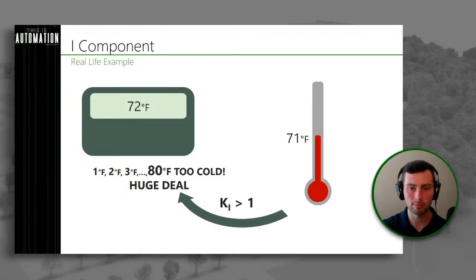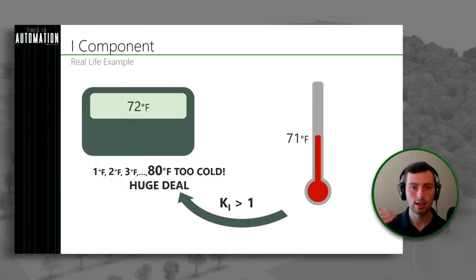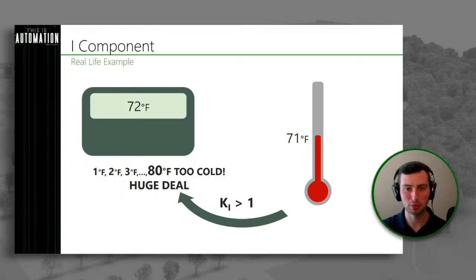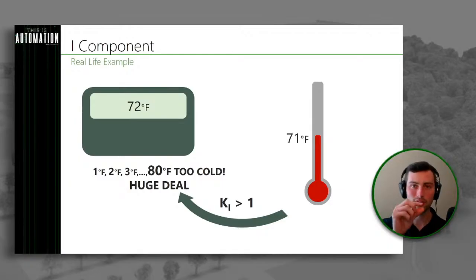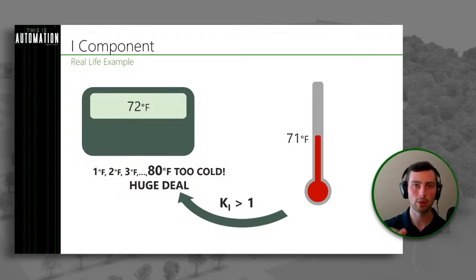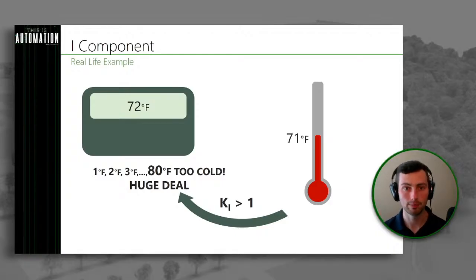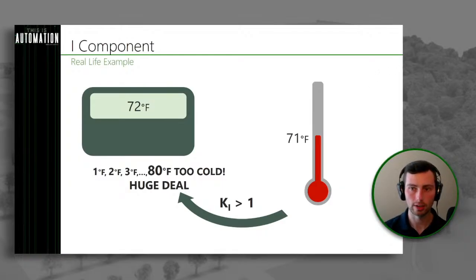Now let's look at what would happen if we had an I component introduced. We have it set to 72 degrees, it's actually 71. With some integral gain, that one degree is going to turn to two degrees, then three degrees, then four degrees. All of a sudden we have something telling us we're way too cold — it's 80 degrees too cold — because we've got this small error building up over time. That's what the integral component does: it looks at the history of the error and accumulates it over time. It's great for steady state error, but can introduce oscillations and other issues.